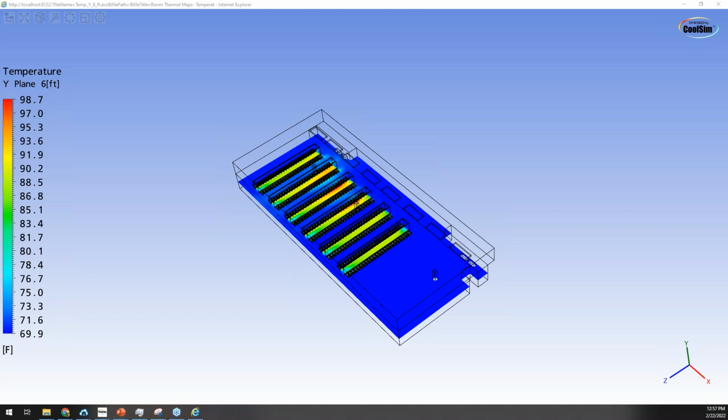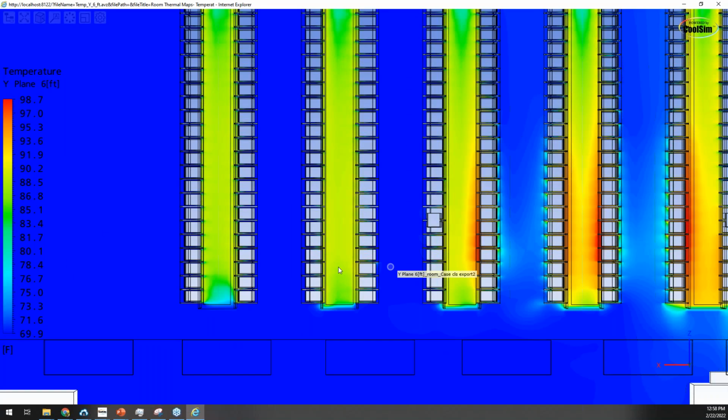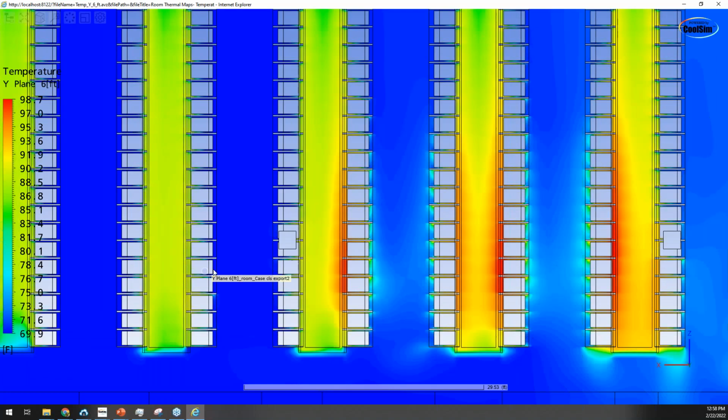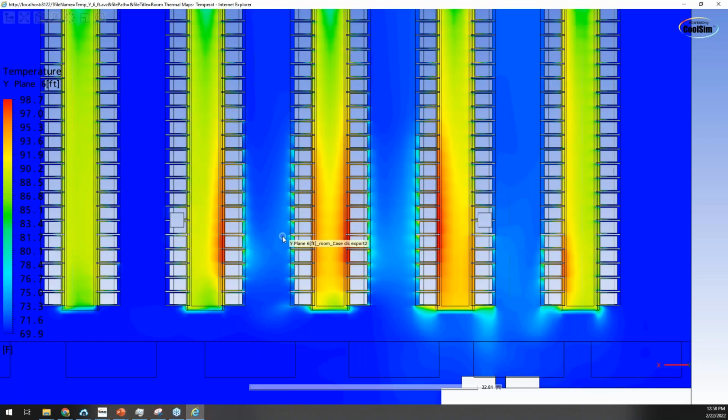There's a question about energy savings. You can model energy savings in this as well. Non-uniform height. Yep. So here's temperature again. We've got leaking racks. I showed this to you earlier, I think. So there's the leakage caused by the high velocities.